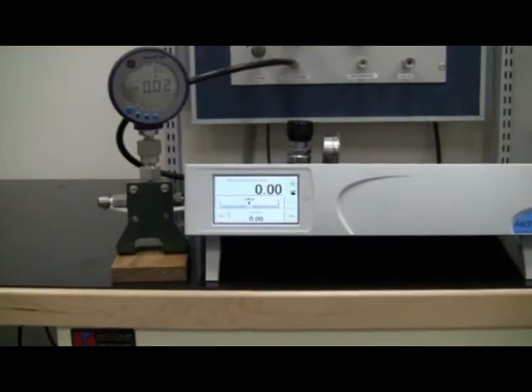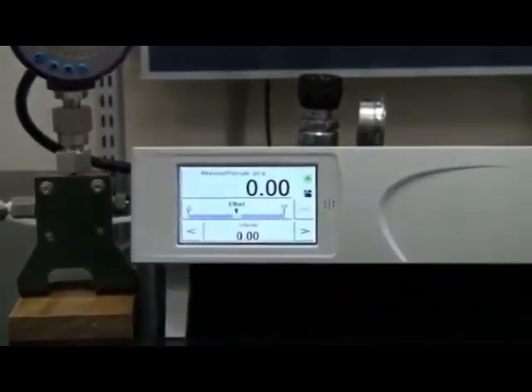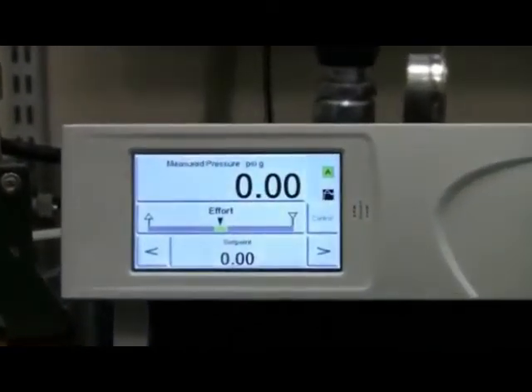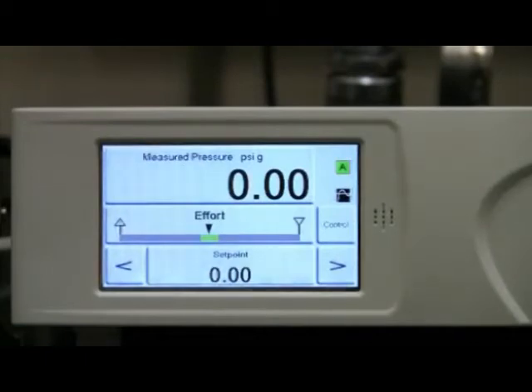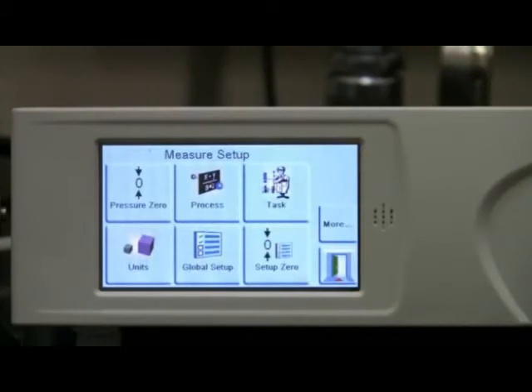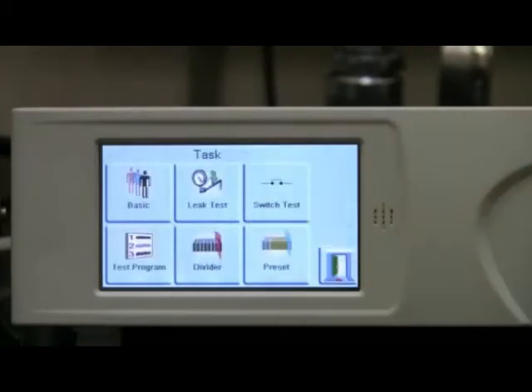PACE 5000 includes a variety of built-in features to make the process of performing different pressure calibration tasks easier. So far, we have been operating in basic mode where we enter the set point value one point at a time. Alternatively, we can select from various other tasks such as performing a leak test, calibrating a pressure switch, test program which we review in a minute, divider which allows us to select a minimum and maximum pressure with evenly spaced intervals, and the preset that allows us to assign a custom sequence of pressure values that may not be evenly divided.